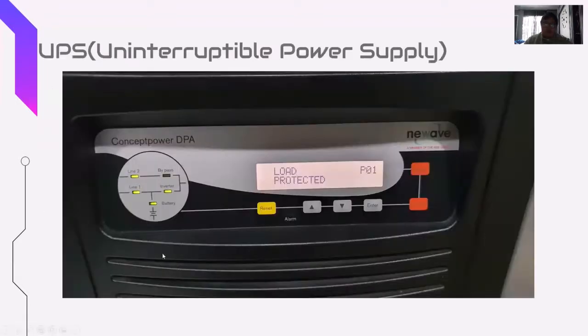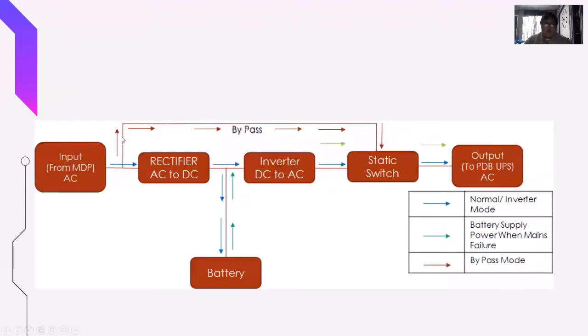So this is one of the UPS controls or modules in a way. Basically the UPS gets its input from the MDP, and then it reaches the rectifier, which converts from AC to DC. It charges the battery and then goes to the inverter, which converts it back to AC, and then its output is put into the PDB UPS. So it charges the batteries.